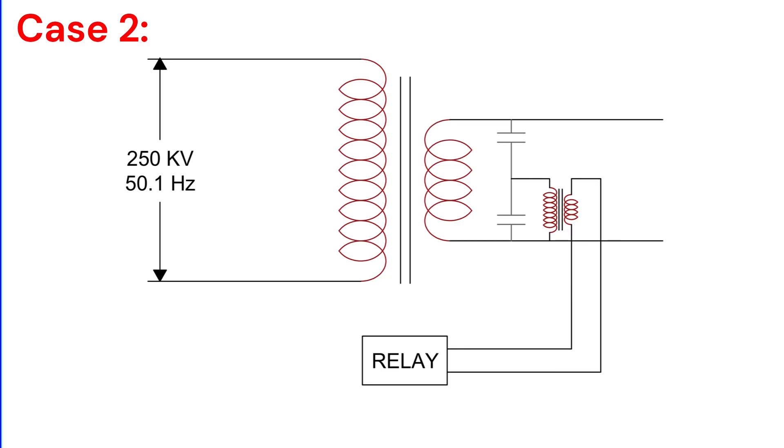So, what's the takeaway? Tap changers play a vital role in preventing overflux tripping, but only if the voltage signal is taken from the secondary side PT. This ensures the transformer operates safely without compromising protection.